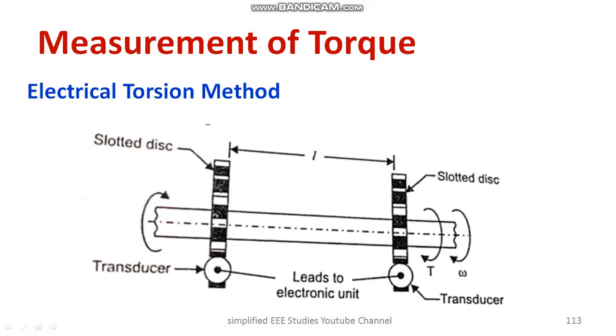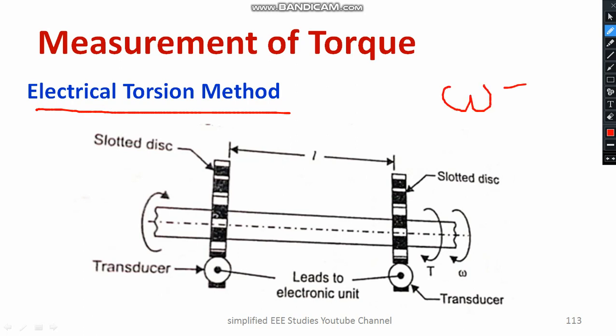For the electrical torsion method: we have a shaft — a mechanical part that may be connected to motors. The shaft is rotating at an angular speed omega, where omega equals 2 pi N by 60, and N is the speed in RPM. Our target is to measure the torque. A slotted disc is used, with shaded and non-shaded slots, and it is coupled with a suitable transducer and electronic measurement unit.